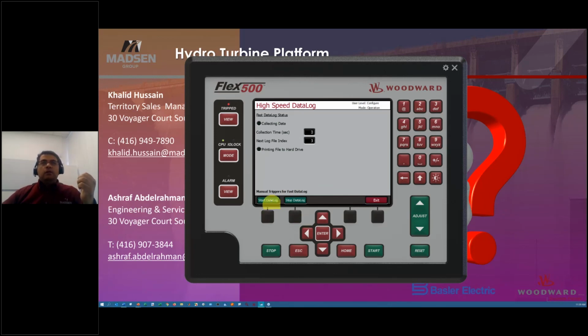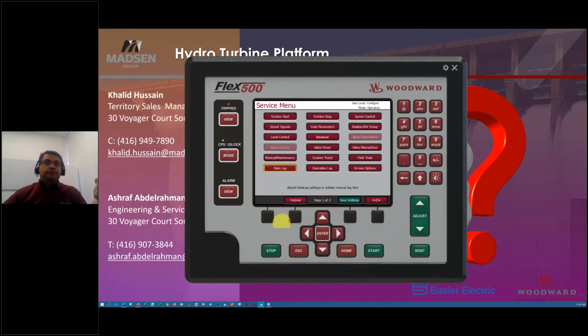Again, as I said to you, if an operator sees an issue and he would like to do some sort of a data log or store the data that comes to the unit, all he has to do is come here and hit the start data log, and all the data related to the turbine at that time will be stored. And then after the phenomenon has ended, he can hit stop data log. So all the data for the phenomenon has been stored inside your PC, so that you can come in, plug in, and take that data and do some more diagnostics to define what the reason was that it happened at that time.